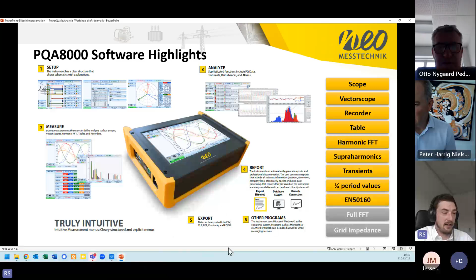And of course, the most important thing, you get one click report according to, I would say, any standard, because you can also define your own PDF document. So it's quite easy to create your own report, which is important for you. But you can also get standard reports like EN 50160, IEC 61000-2-2 or -2-4 with the 3 classes. There's also the possibility to add local distributions, like in Austria for example, the DACH standard for current limitation.